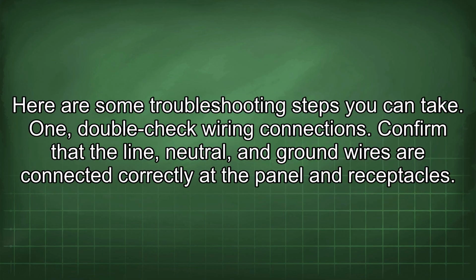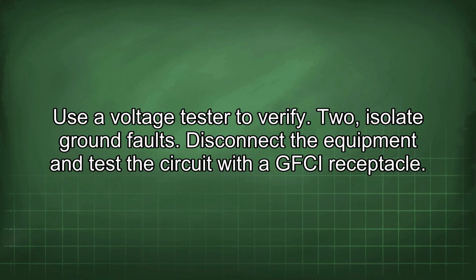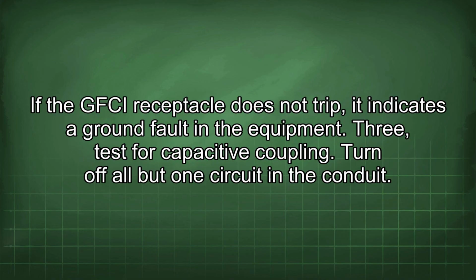Here are some troubleshooting steps you can take. 1. Double-check wiring connections. Confirm that the line, neutral, and ground wires are connected correctly at the panel and receptacles. Use a voltage tester to verify. 2. Isolate ground faults. Disconnect the equipment and test the circuit with a GFCI receptacle. If the GFCI receptacle does not trip, it indicates a ground fault in the equipment.